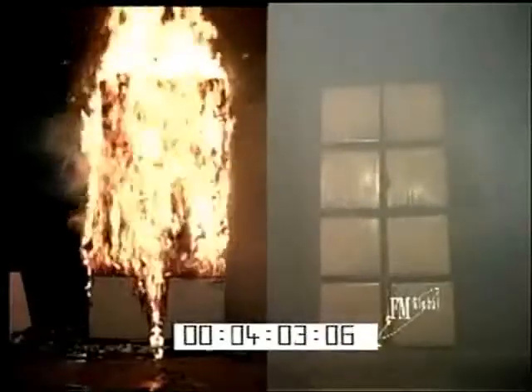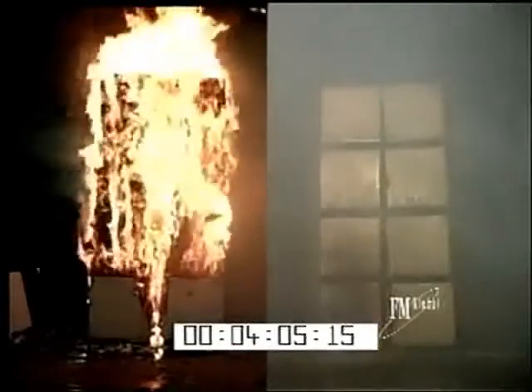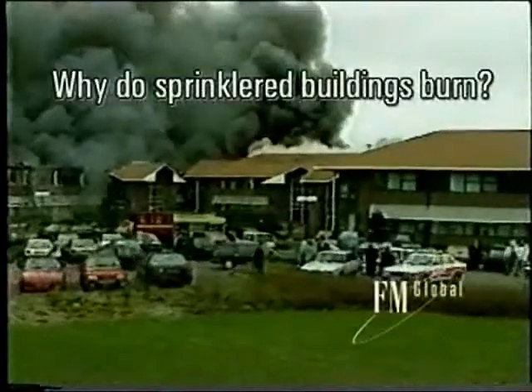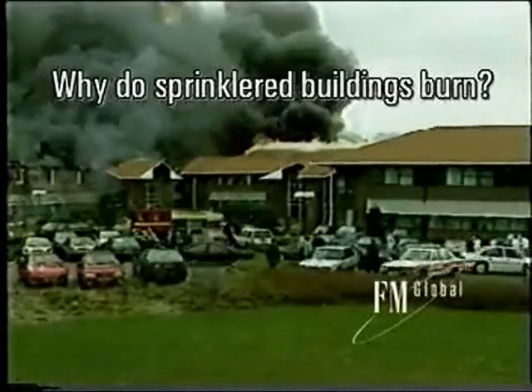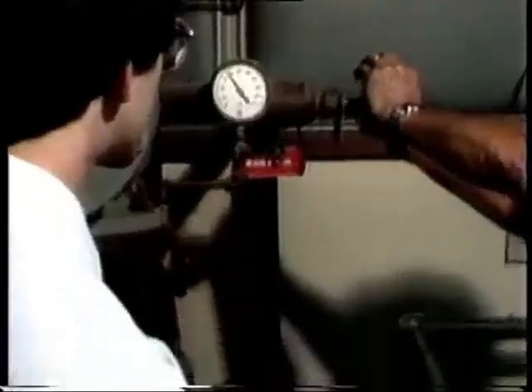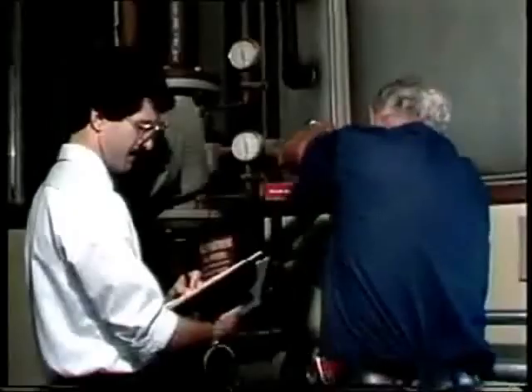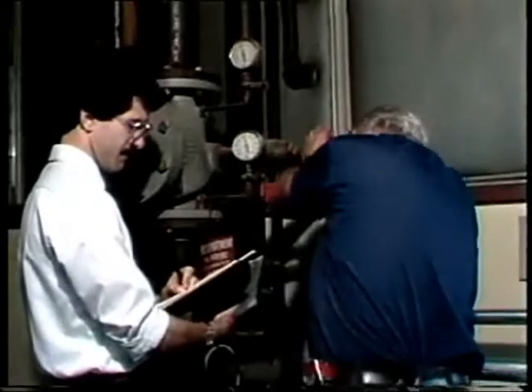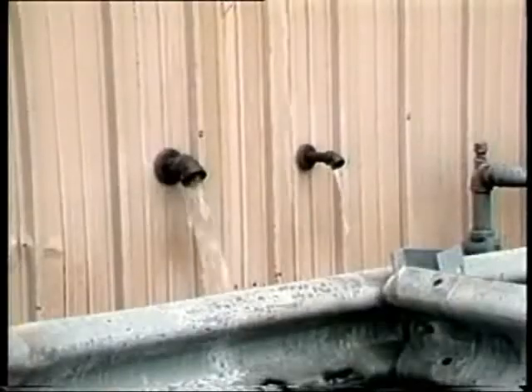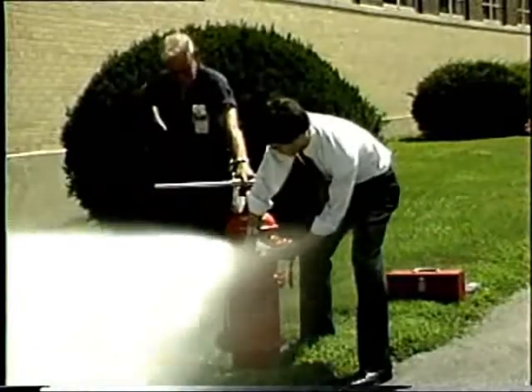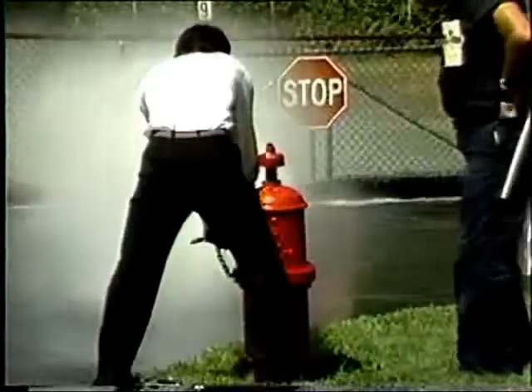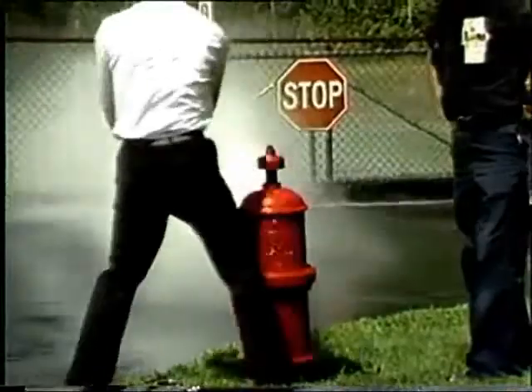An adequate sprinkler system is a key ingredient in fire protection. Tests have shown substantial differences in fires in sprinklered versus non-sprinklered structures. But if sprinklers can be that effective, then why do sprinklered buildings burn? There are several reasons. One problem is design deficiencies in the water supply system. An adequate system should be designed for a particular occupancy, providing maximum water volume and pressure needed to fight fire for the most severely anticipated hazard.